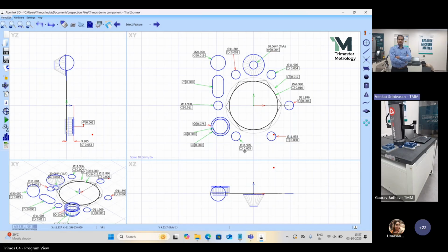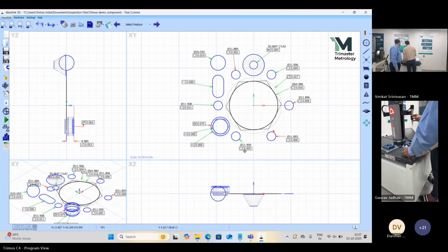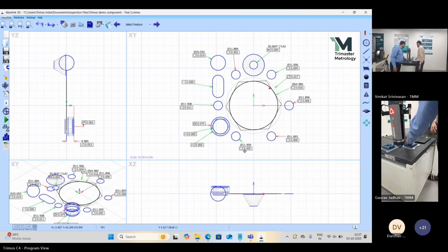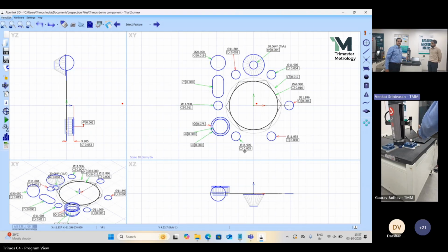Basically it's a standard sphere that we use for probe calibration. For the calibration of this, it is quite simple because again there is an automated program and you just set the probe here and you select the respective option. So we just set the sphere like this and there's an option on the screen. We bring it up above and we say start, and for both vertical as well as horizontal probes, it will run an automatic cycle to run the calibration cycle and calculate the probe constants for each.